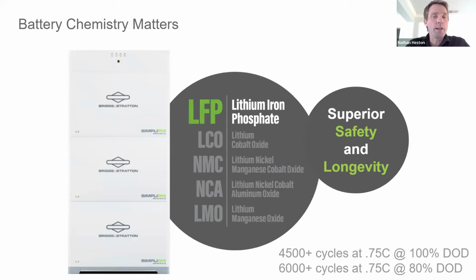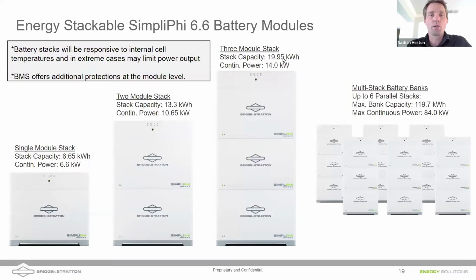This battery is using LFP chemistry, as I mentioned, for superior safety and longevity, 4,500 cycles at 0.75 C. You're going to see here in a minute that we're able to run this battery a lot harder, a lot faster than some of our previous offerings. If we slow things down a little bit, if we're doing only 80% depth of discharge, we're getting over 6,000 cycles here, and we say 6,000 plus because this is based on rapid charge discharge. We expect that the average customer is not going to be continuously charging at 0.75 C, which means a charge cycle in an hour and 20 minutes, charge and discharge in an hour and 20 minutes.